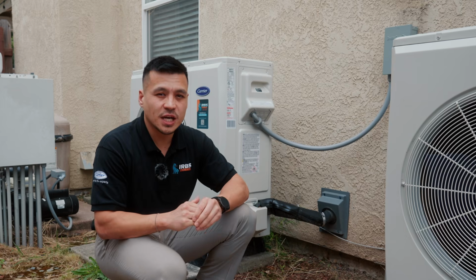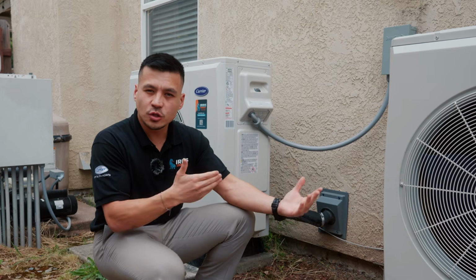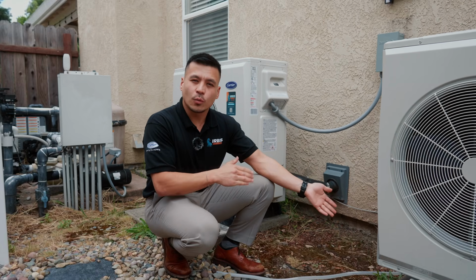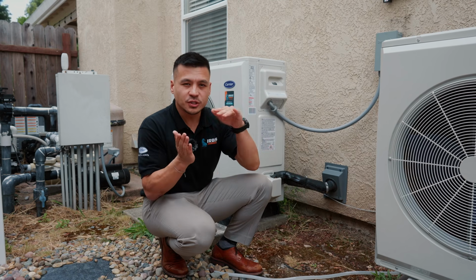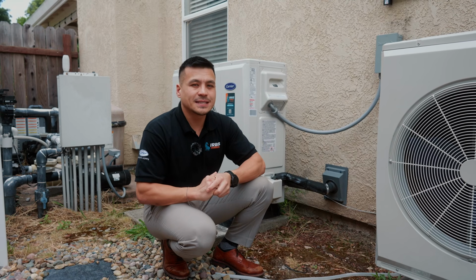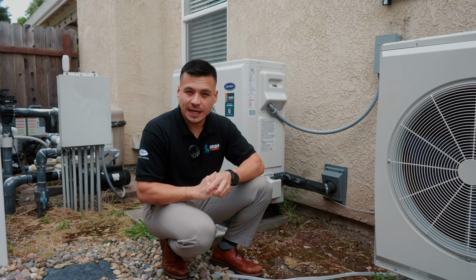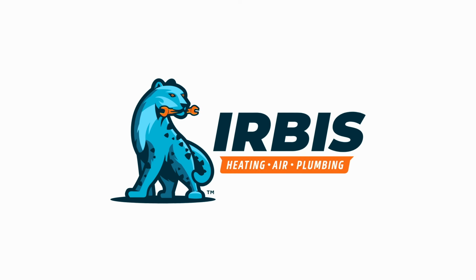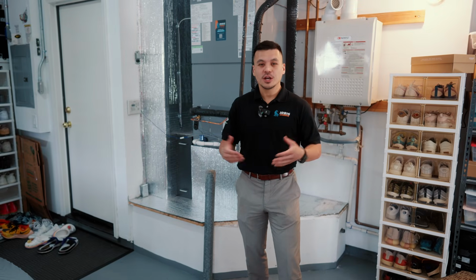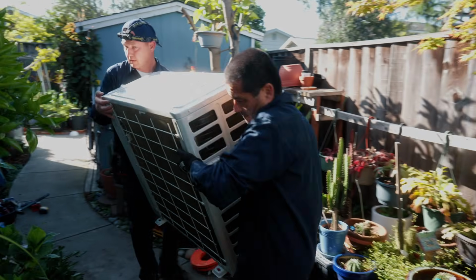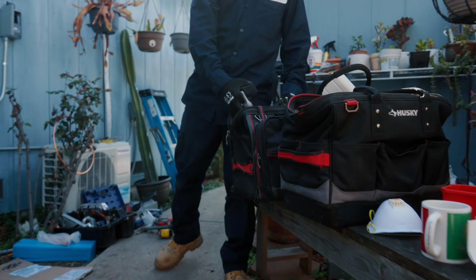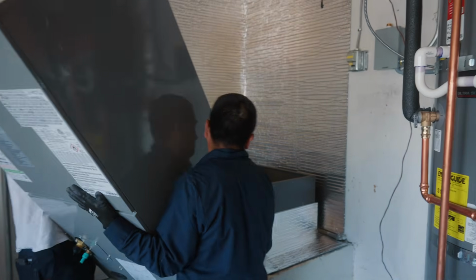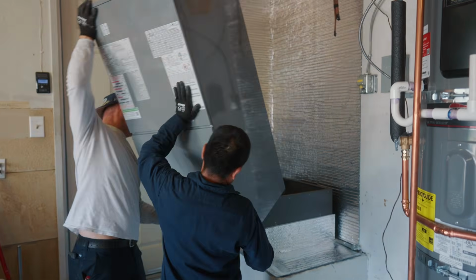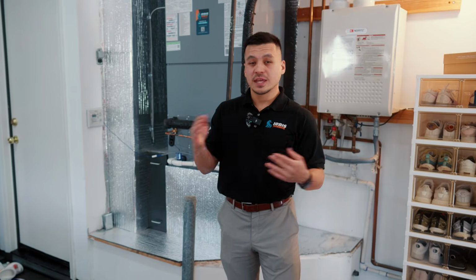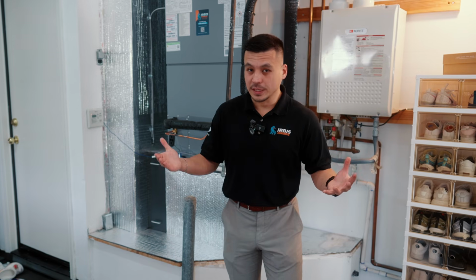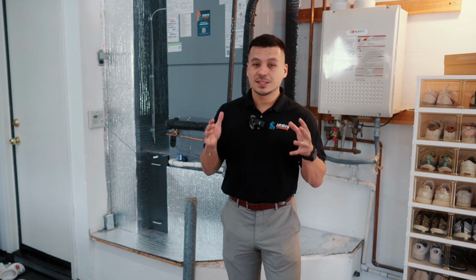So make sure to check what type of refrigerant your existing system has and what type of refrigerant you are switching to, and from there you can decide whether you need to upgrade your line set or not. While replacing the air conditioner or adding an air conditioner to your existing heating system, very often your contractor may recommend you replace your heating system as well, or if you're replacing it with a heat pump, you will replace it anyway. How to approach this situation?